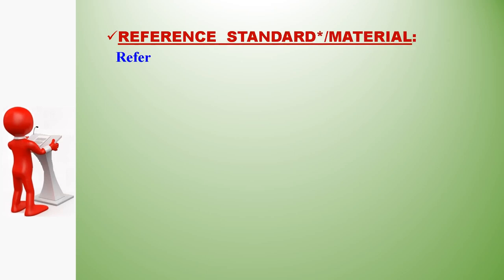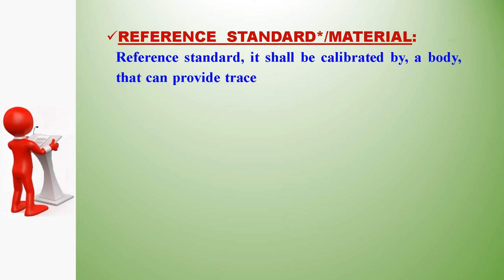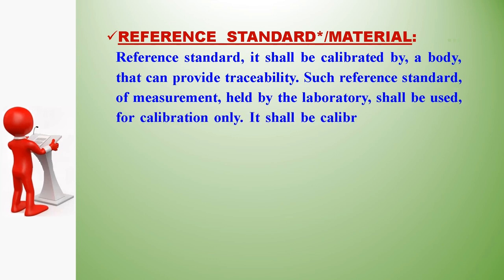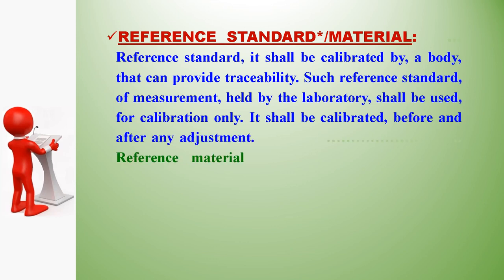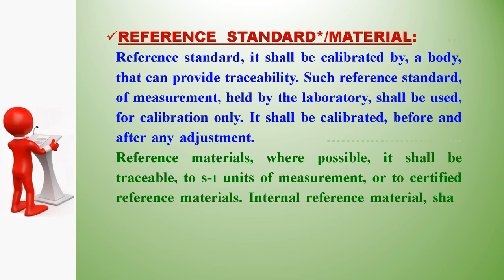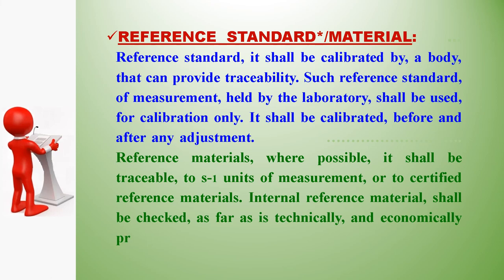Reference standards shall be calibrated by a body that can provide traceability. Such reference standards held by the laboratory shall be used for calibration only, and shall be calibrated before and after any adjustment. Reference materials, where possible, shall be traceable to SI units of measurement or to certified reference materials. Internal reference materials shall be checked as far as is technically and economically practical.